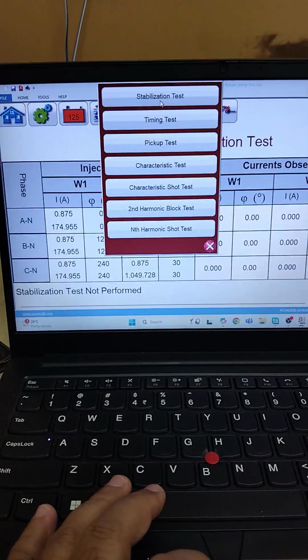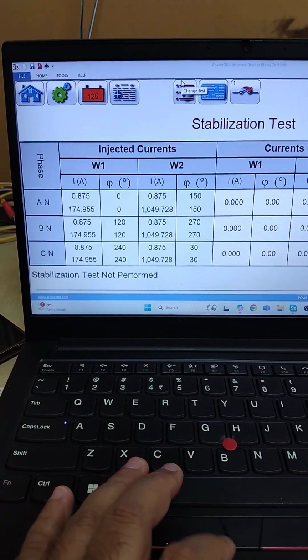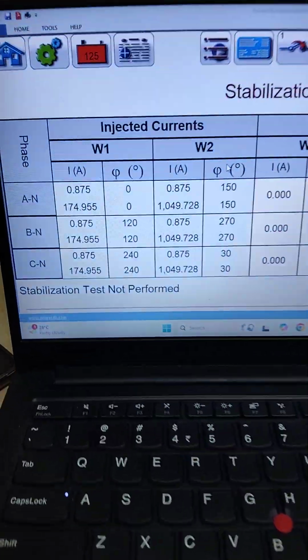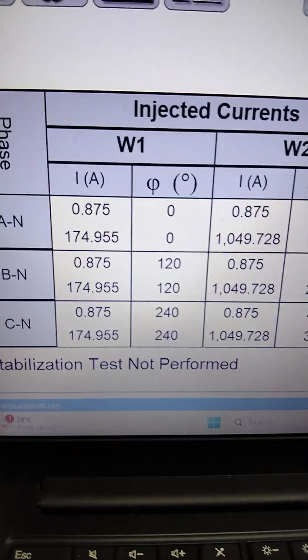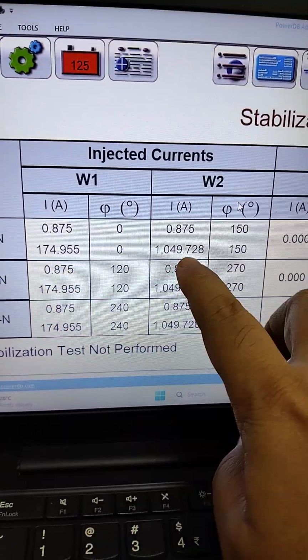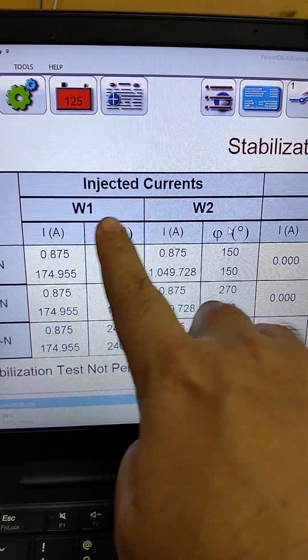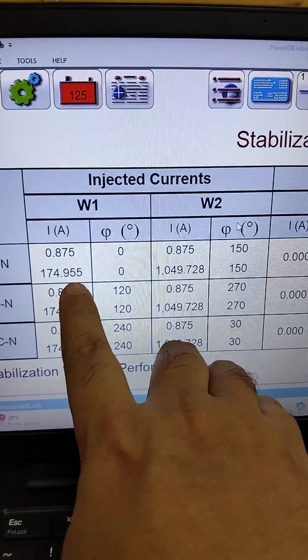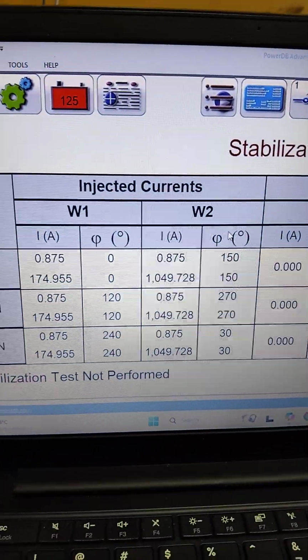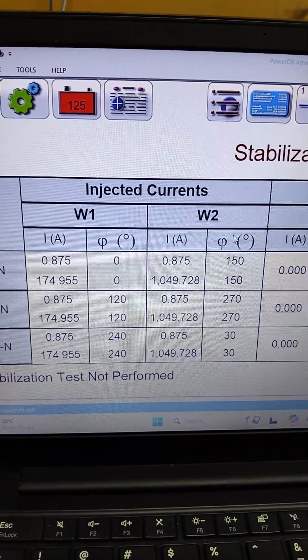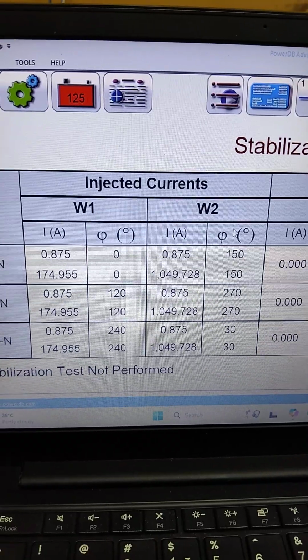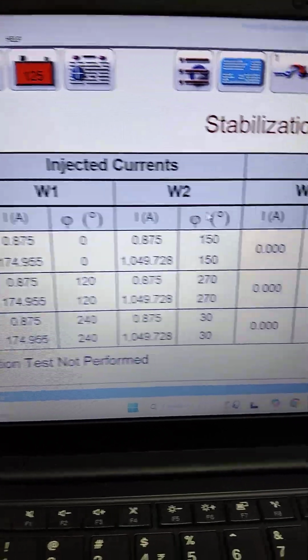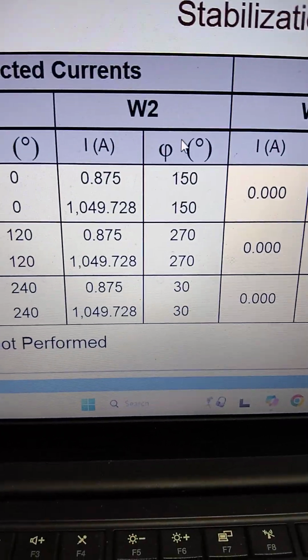So first of all we need to do the stabilization test. So select the stabilization test. You'll see this window. In this you can see that the currents on the HV and LV side, winding 1 and winding 2, are injected based on the 1 PU criteria of the device, that is 20 MVA, 175 is 1 PU on the 66 kV side and 1050 on the LV side.